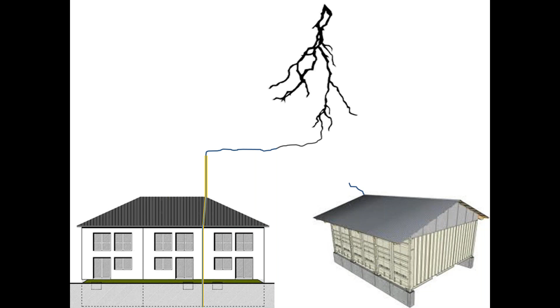Now instead of the previous lightning protection system, we have a very tall air termination and one down conductor. This is a wrong installation. See what happens when that same lightning step leader comes. Because of the height of this air termination, the step leader, instead of going to the neighbor's building, may come to our building of concern.